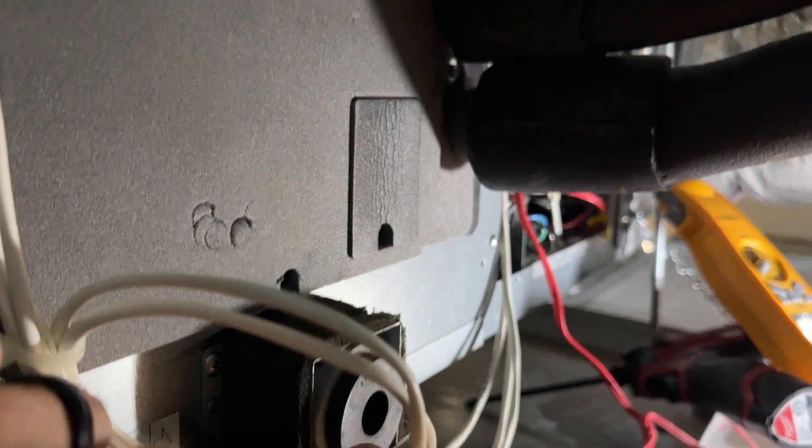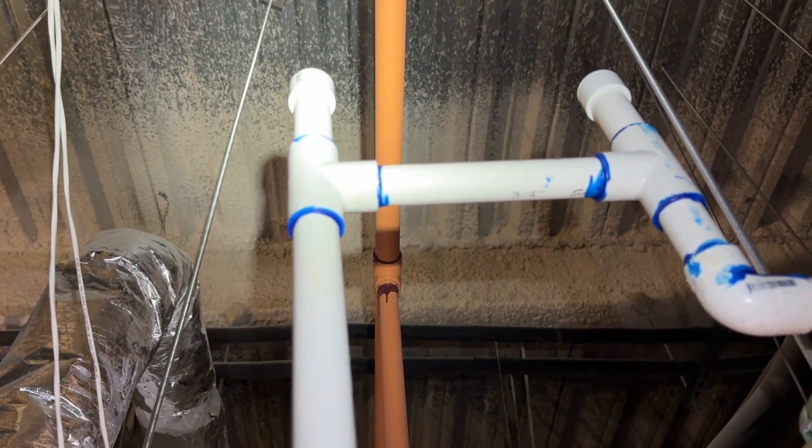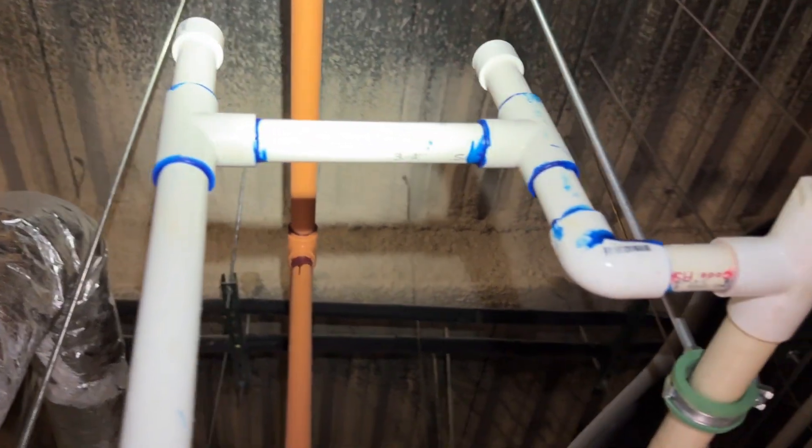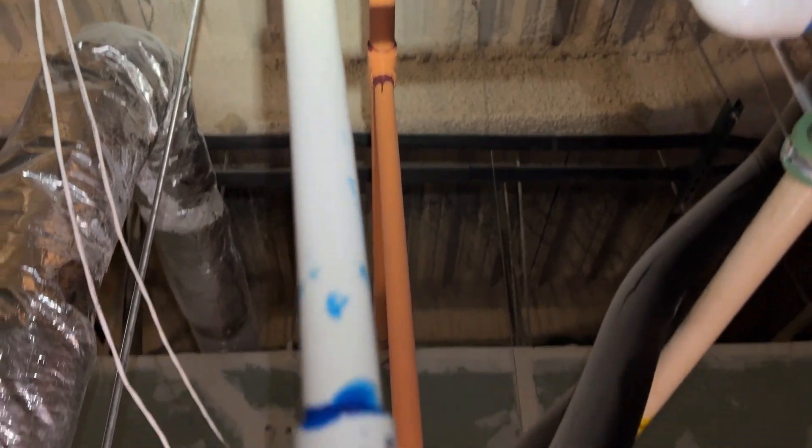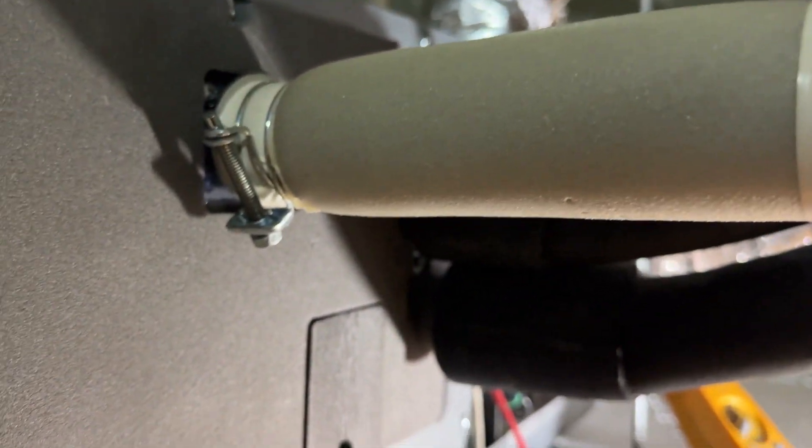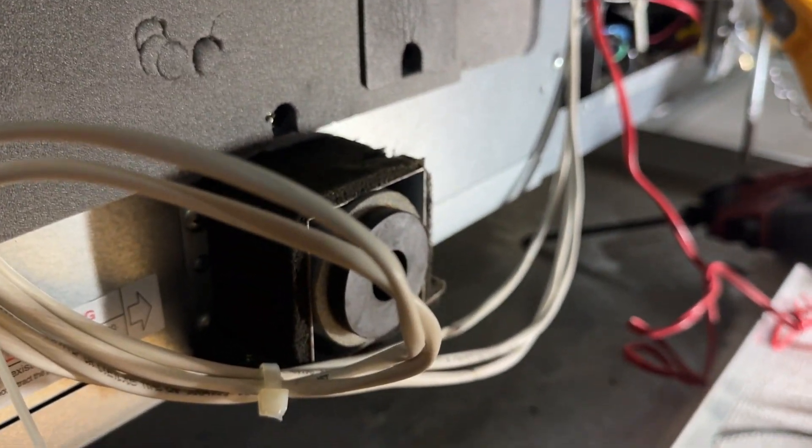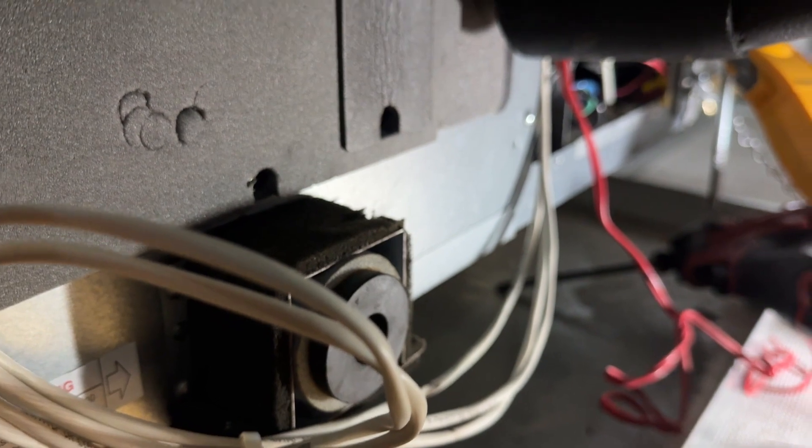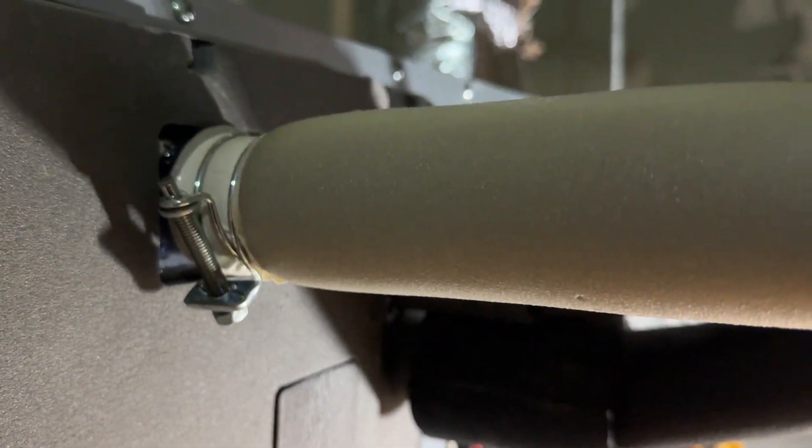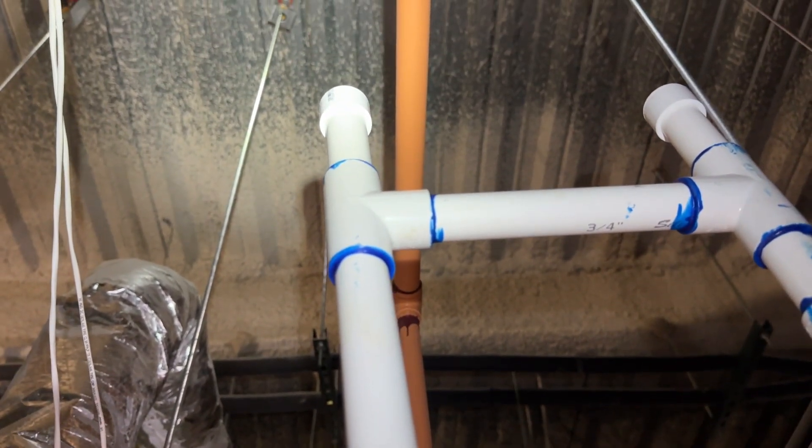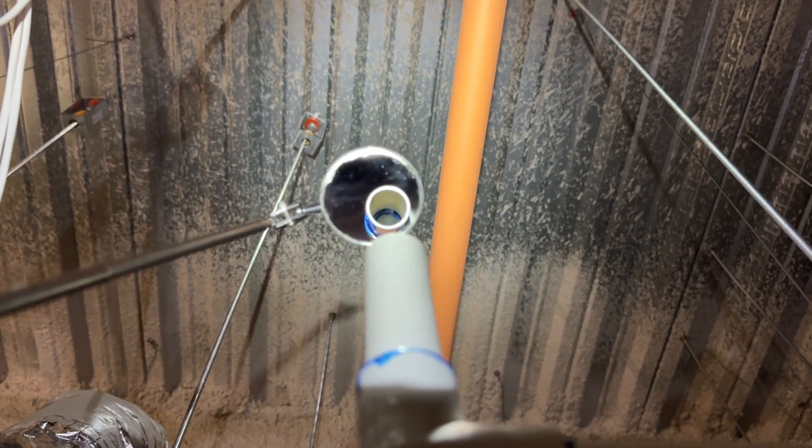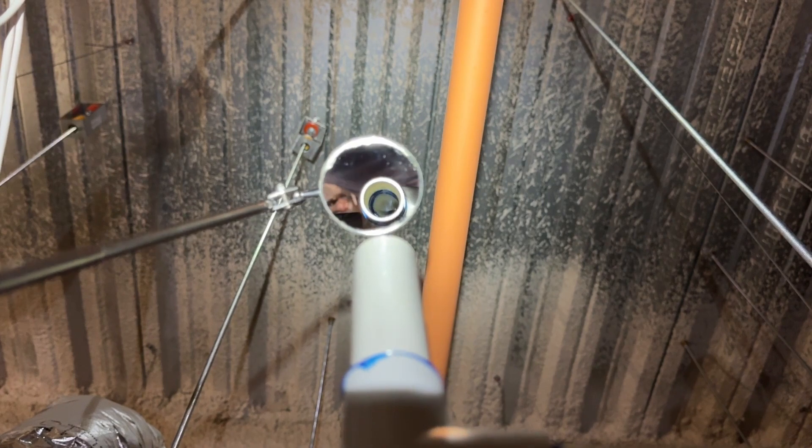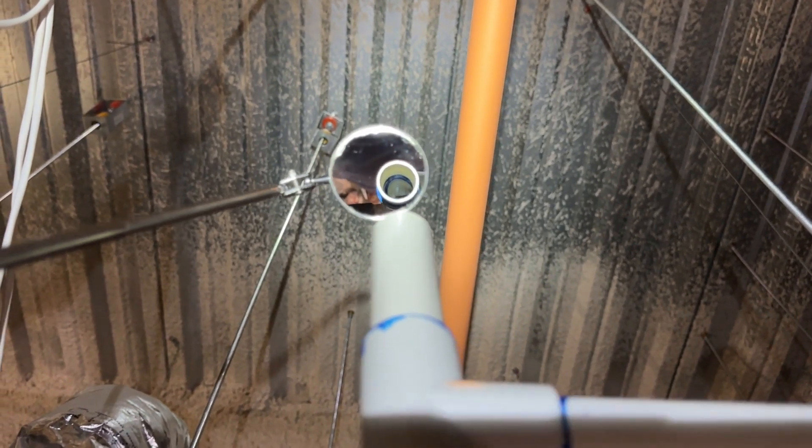But again when you're troubleshooting never make assumptions unless you have done the experiments. I've never locked one up. Here's the drain for the pump. Of course if you're gonna gravity drain it you do it out of there and I'm not really liking this. I need to look and see what the spec is but I'm not sure that that little pump has that kind of lift. What I might do in the meantime is just drain the water down from there and see how much water we have built up. May try looking down in there and see what's going on. Alright so yep we've got standing water right up there at the level of the T.